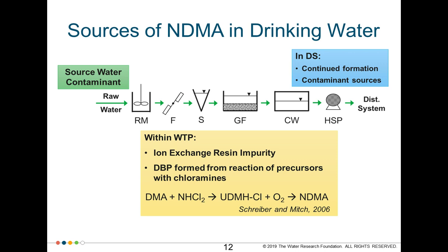NDMA was first discovered in drinking water in 1989 in Ontario, Canada. There are a number of potential sources of NDMA in drinking water. Some plumes of NDMA contamination come from liquid rocket fuel production, so it can occur as a source water contaminant. Research has shown that ion exchange resins can leach NDMA and other nitrosamines. The primary formation mechanism for NDMA in drinking water is from reaction of precursors with chloramines. Schreiber and Mitch in 2006 postulated that dichloramine in particular was important for this reaction. Precursors can be watershed-derived from agricultural or wastewater discharges, or polymer-derived — polydadmac and polyamine-based polymers have been found to react with chloramines to form NDMA.